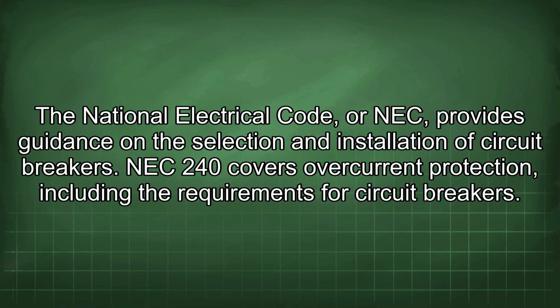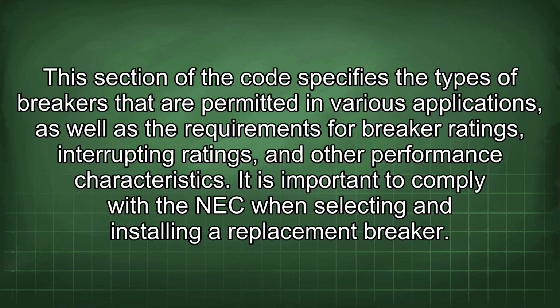The National Electrical Code, or NEC, provides guidance on the selection and installation of circuit breakers. NEC 240 covers overcurrent protection, including the requirements for circuit breakers. This section of the code specifies the types of breakers that are permitted in various applications, as well as the requirements for breaker ratings, interrupting ratings, and other performance characteristics. It is important to comply with the NEC when selecting and installing a replacement breaker.